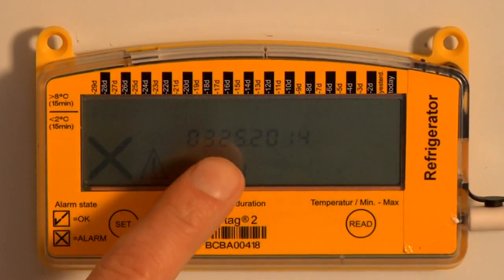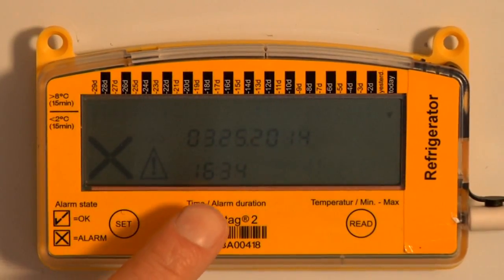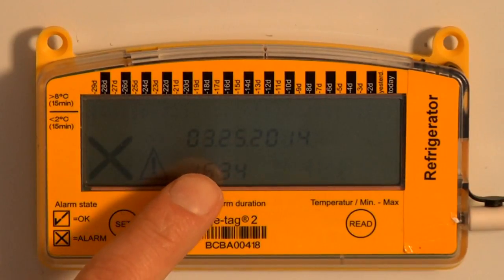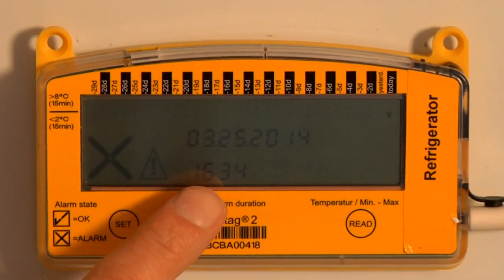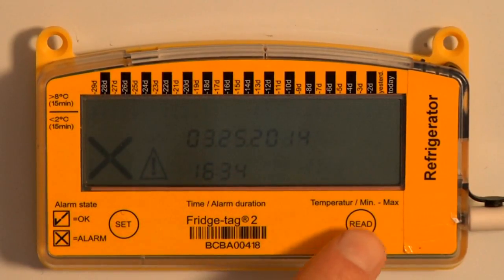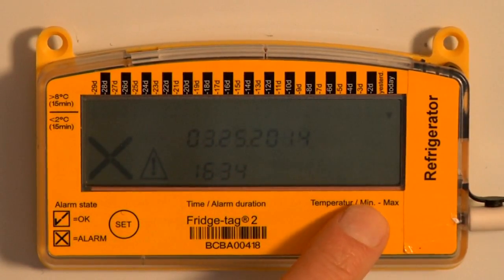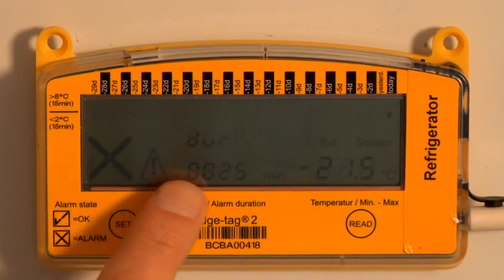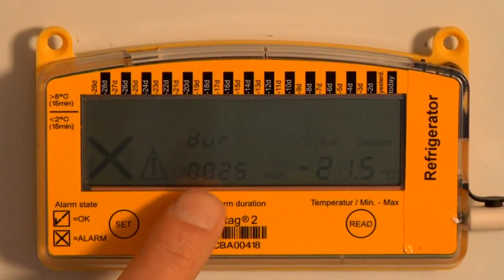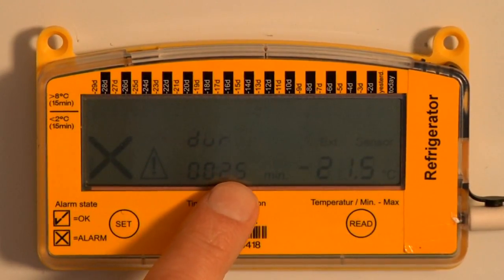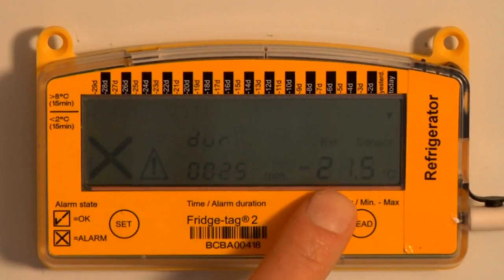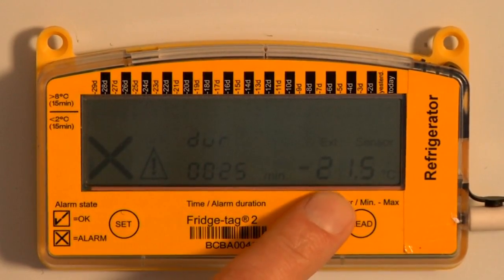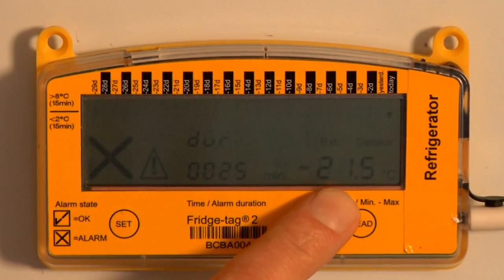The low temperature alarm occurred today at 16:34, or 4:34 in the afternoon. The duration was 25 minutes below 2°C, and the lowest temperature observed was negative 21.5°C — quite cold.